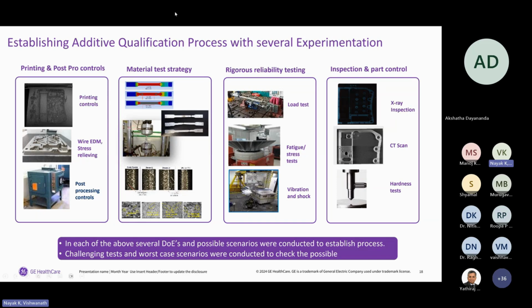And coming to the reliability testing, definitely we do an IEC factor of safety load testing. We do fatigue testing because typically in IEC requirements for medical devices, there are some regulatory requirements where we say that the factor of safety has to be so and so. Now, when we do that, there are two options. Either you demonstrate it by test, or you prove it with a good amount of finite element analysis and also do some calculations and show it. So typically we do both.